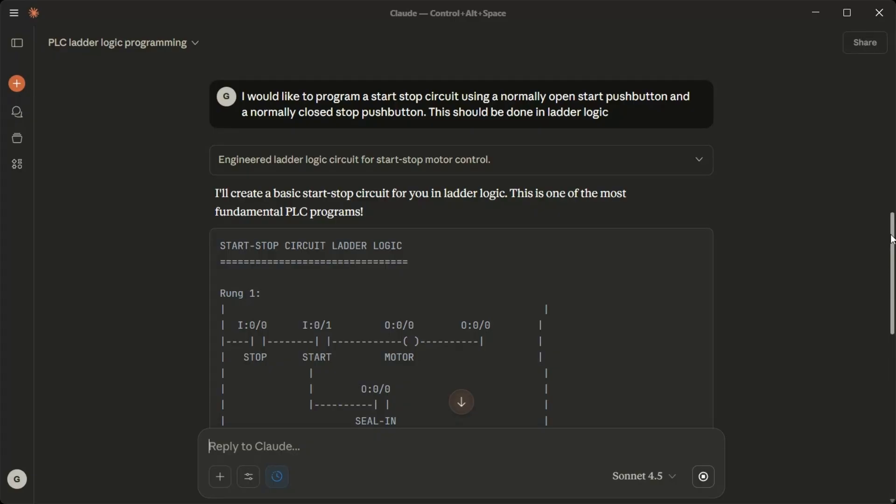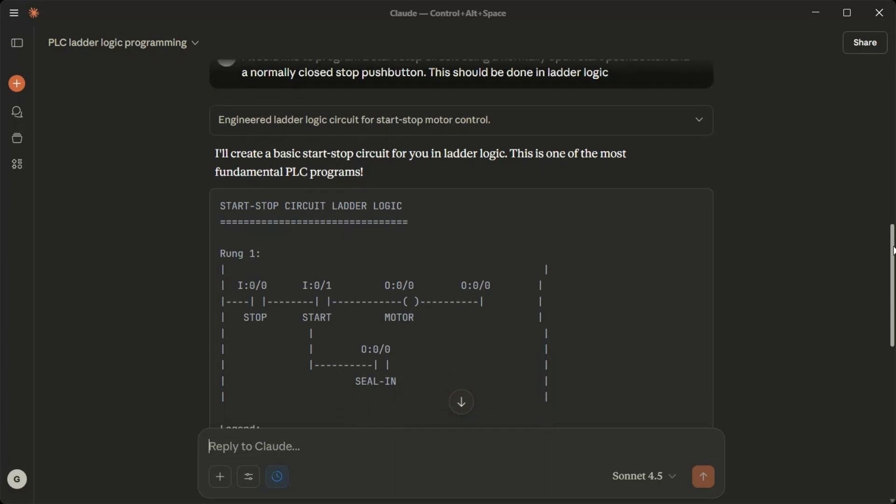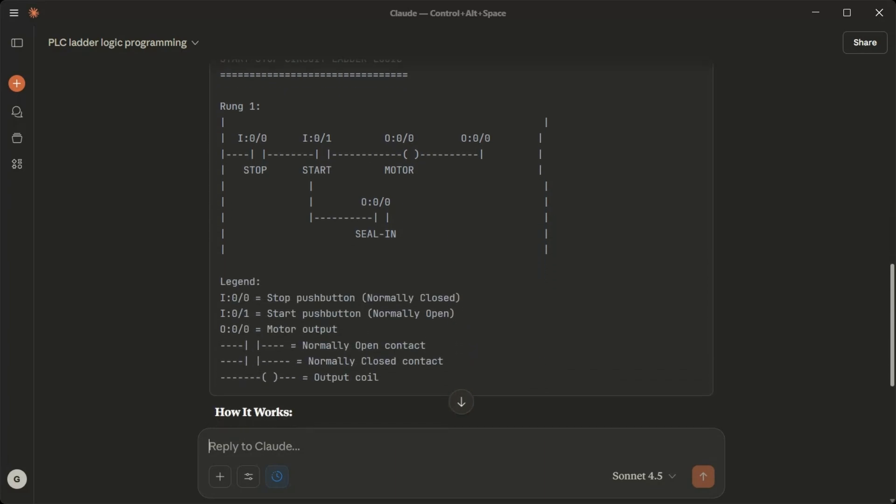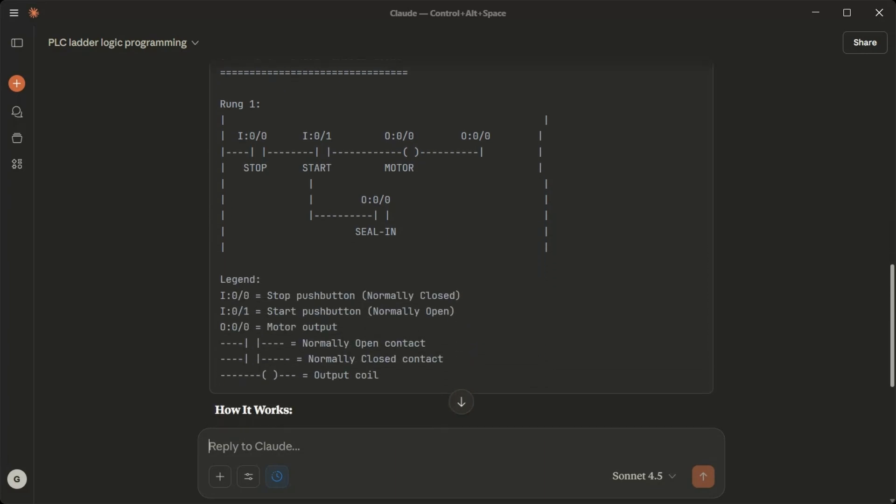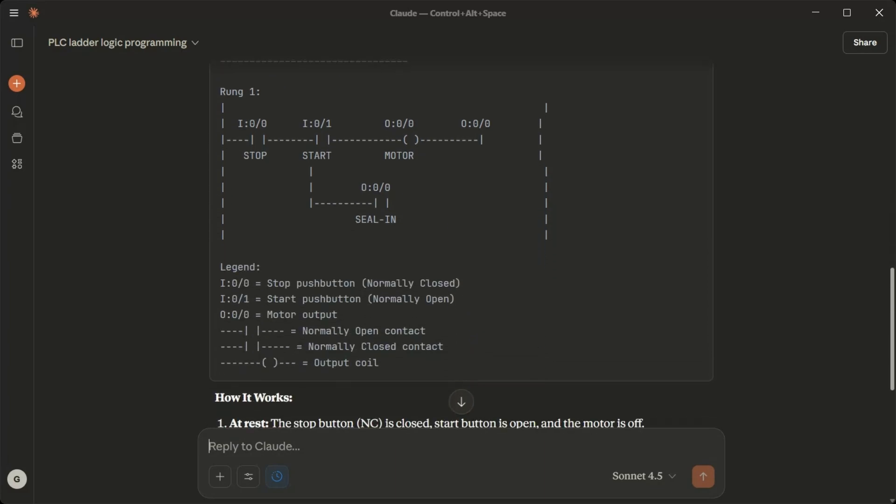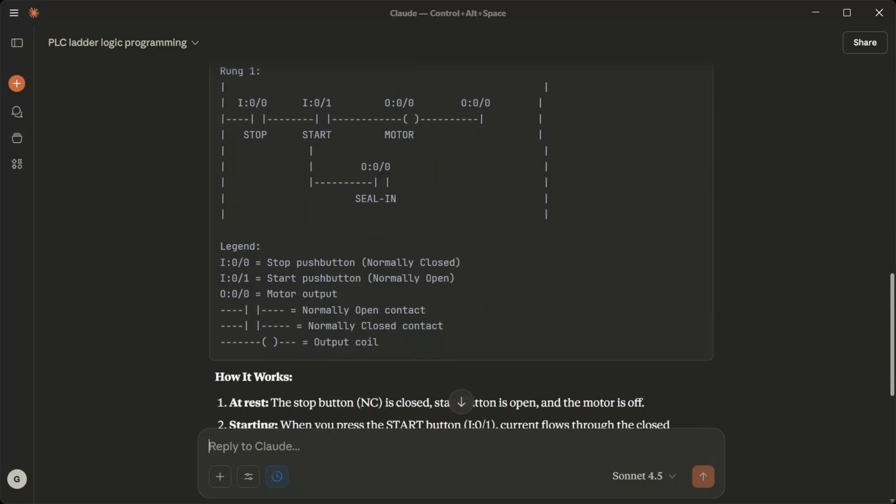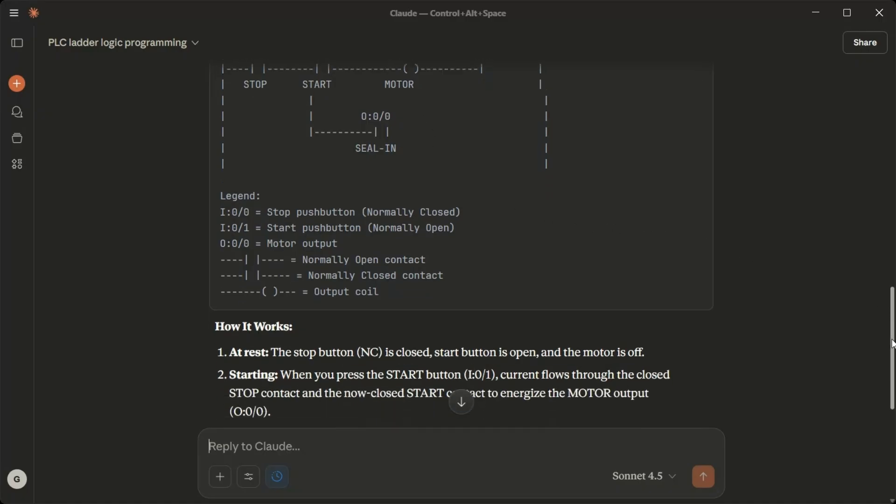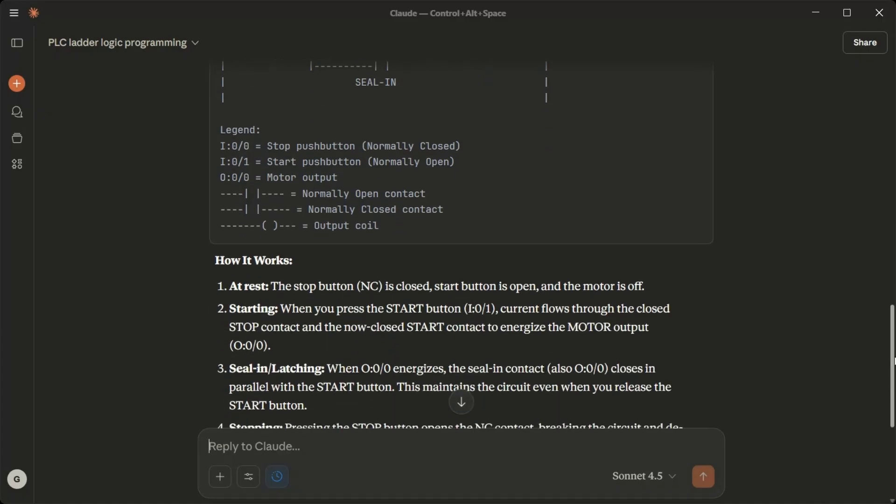Seal in/latching: When O:0/0 energizes, the seal in contact also O0/0 closes in parallel with the start button. This maintains the circuit even when you release the start button. Stopping: Pressing the stop button opens the NC contact, breaking the circuit and de-energizing the motor. The seal in contact also opens and the circuit resets.